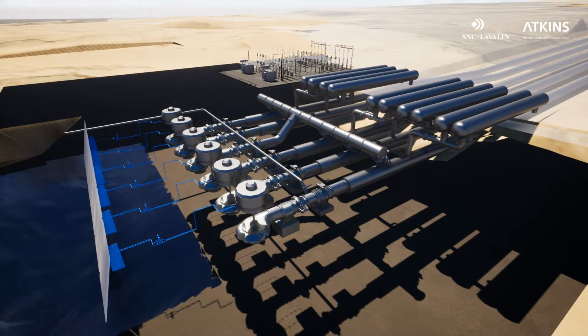To minimize the starting loads and optimize the electrical systems, a bypass recirculating line is provided to reduce the hydraulic load while each pump accelerates to the duty speed. A sophisticated bus main system allows the standby pump to deliver to any of the 5 rising mains, which will ensure high availability of the full 200 cubic meters per second pumping station design capacity. The simplicity of the pumping station layout is conducive to ease of access for operation and maintenance.